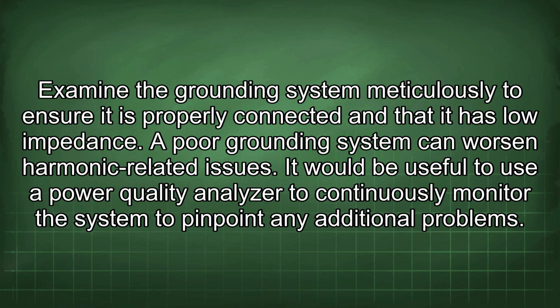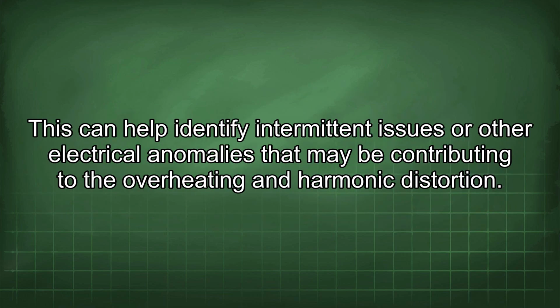Examine the grounding system meticulously to ensure it is properly connected and that it has low impedance. A poor grounding system can worsen harmonic-related issues. It would be useful to use a power quality analyzer to continuously monitor the system to pinpoint any additional problems. This can help identify intermittent issues or other electrical anomalies that may be contributing to the overheating and harmonic distortion.